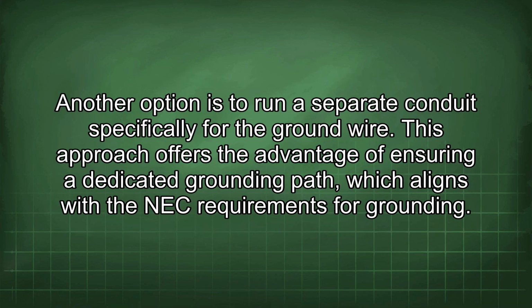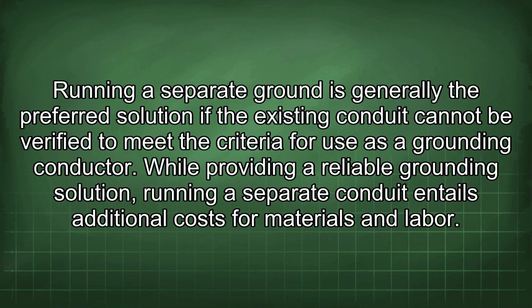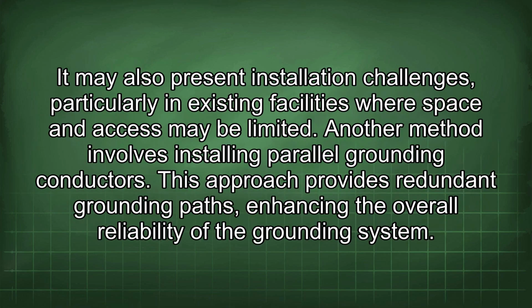Another option is to run a separate conduit specifically for the ground wire. This approach offers the advantage of ensuring a dedicated grounding path which aligns with the NEC requirements for grounding. Running a separate ground is generally the preferred solution if the existing conduit cannot be verified to meet the criteria for use as a grounding conductor. While providing a reliable grounding solution, running a separate conduit entails additional costs for materials and labor. It may also present installation challenges, particularly in existing facilities where space and access may be limited.